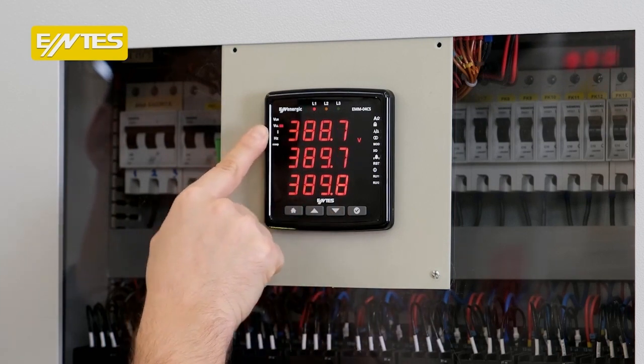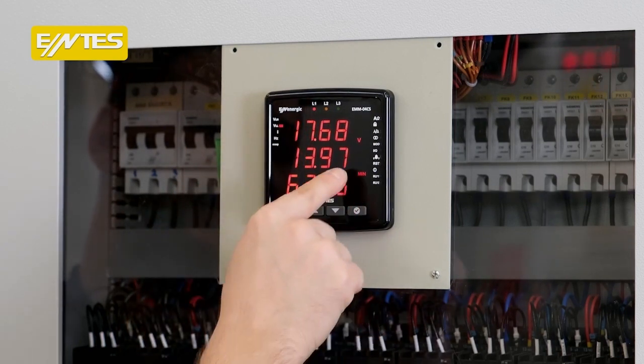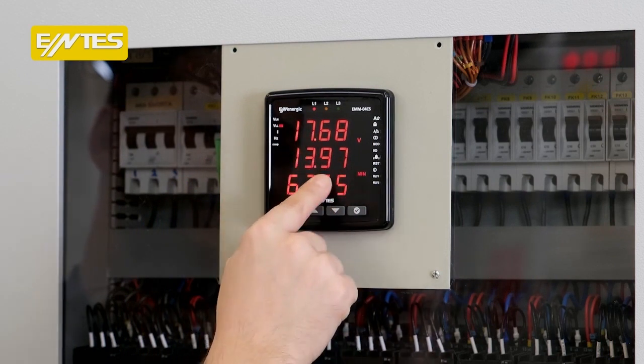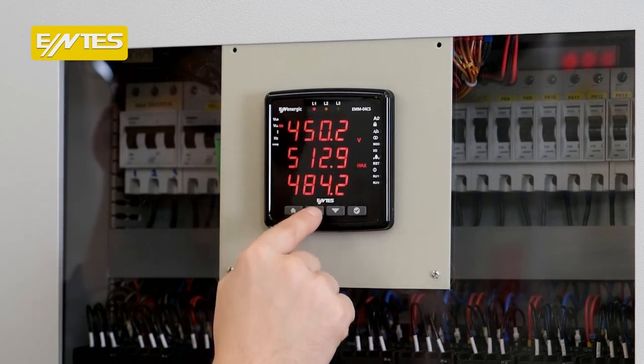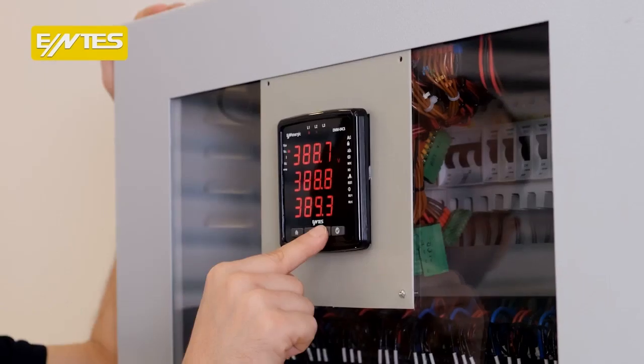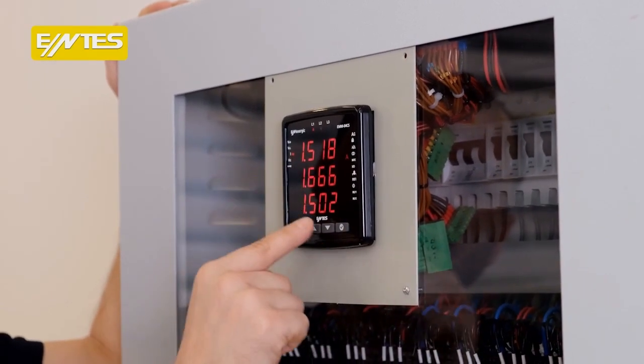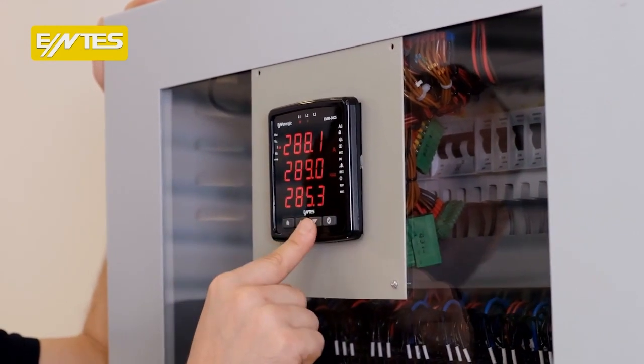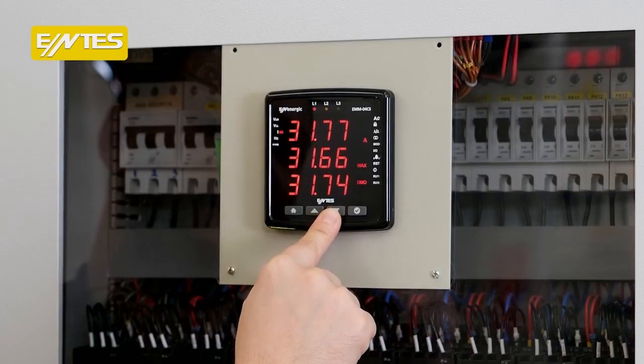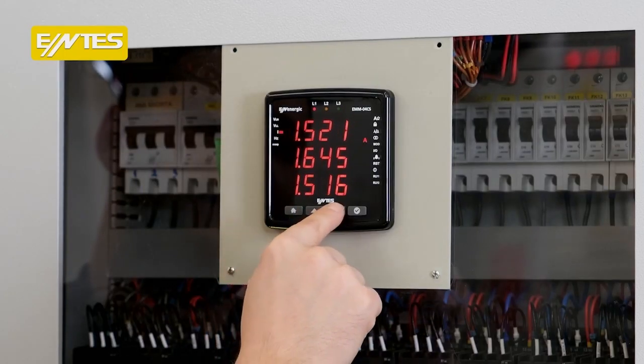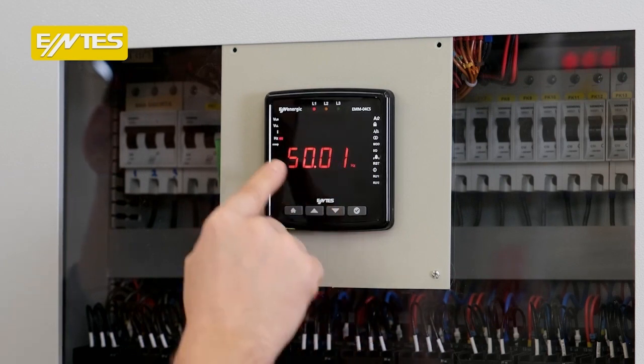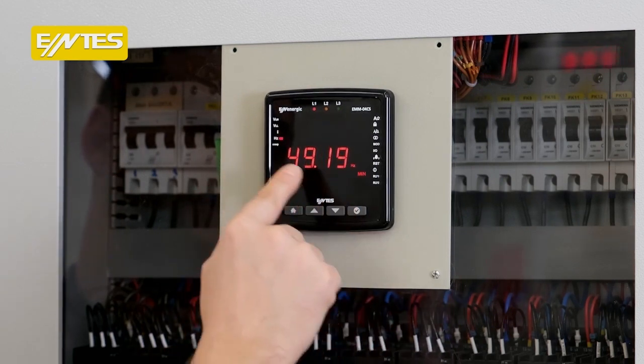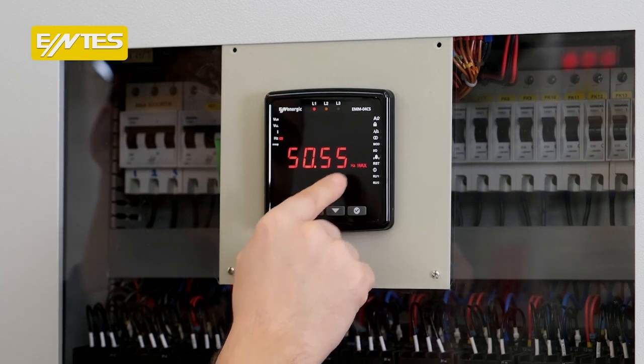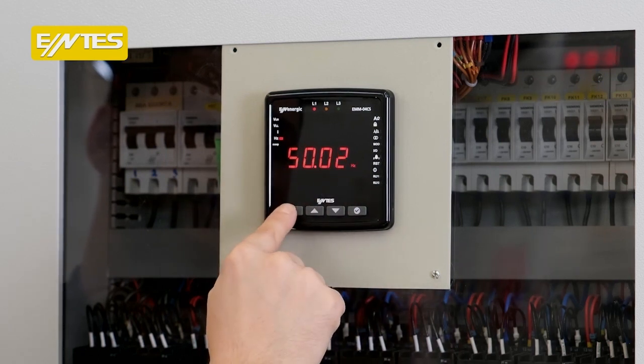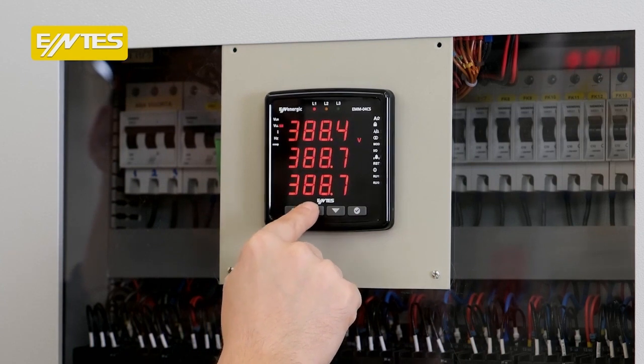We arrive at the phase-to-phase measurement. Press the OK button once more. There are the minimum and maximum voltage levels that it measures. We arrived at the current with the down button. There are the minimum measured current, maximum measured current, and demands in the current. Here we can see the demands. We press the down button, we arrive at the frequency. We press the OK button. We have reached the minimum and maximum levels in frequency. We are able to observe the measurements in this manner.